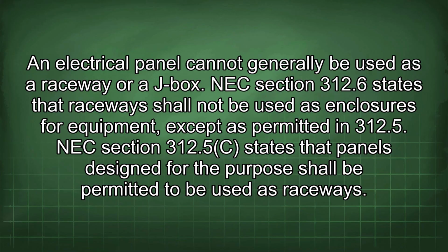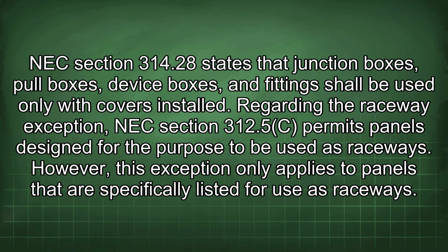An electrical panel cannot generally be used as a raceway or a J-box. NEC Section 312.6 states that raceways shall not be used as enclosures for equipment, except as permitted in 312.5. NEC Section 312.5(C) states that panels designed for the purpose shall be permitted to be used as raceways. NEC Section 314.28 states that junction boxes, pull boxes, device boxes, and fittings shall be used only with covers installed.